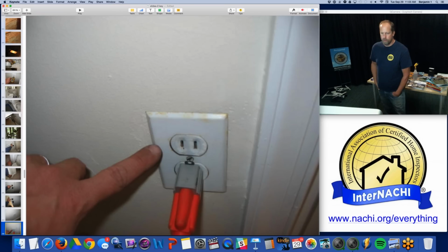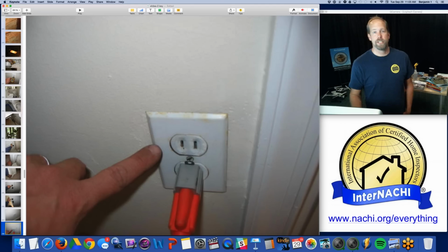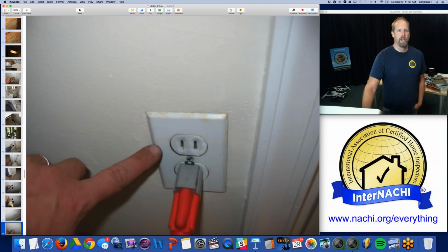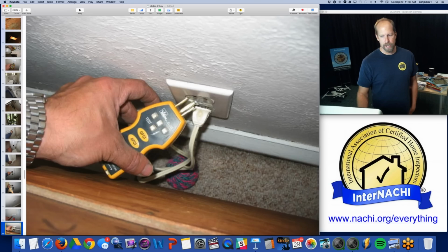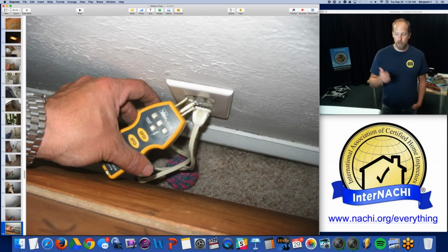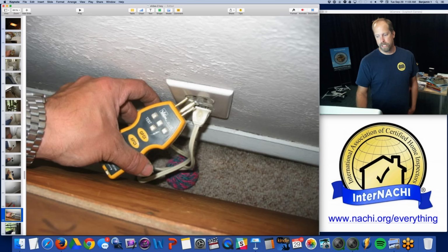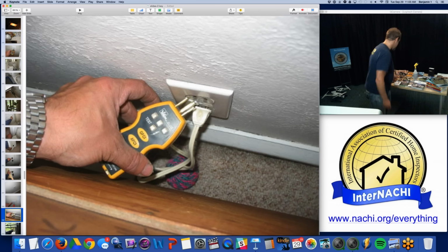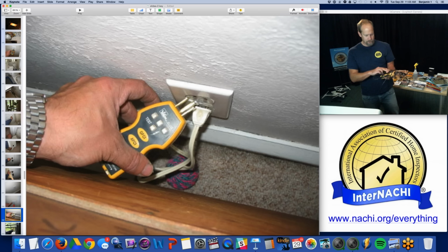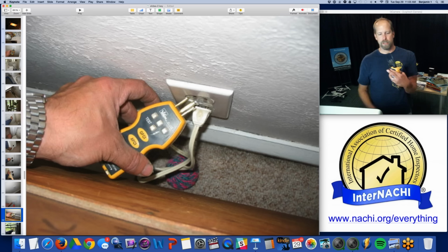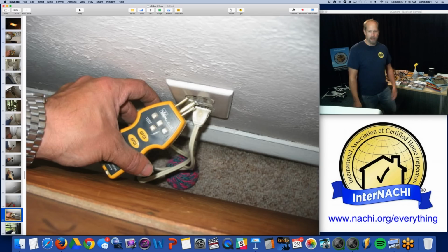Two-prong receptacles. They're using a cheater right here, improperly installed. No big deal, but your client ought to know this is an older home and has older wiring in it. And they'll be surprised when they try to plug in a three-prong device into a two-prong receptacle. Not my clients, because I tell them. Actually take a picture and then demonstrate. This is my GFCI tester with the three prongs trying to plug into something with two prongs. Right, so it's not going to work. So the picture really is 1,000 words. If I had to describe that in words, I'd be writing all day.